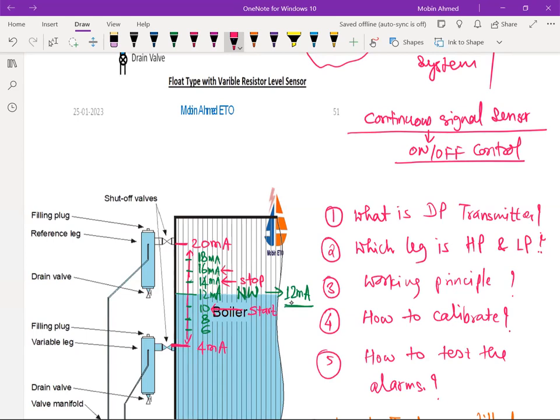Then at 16 milliampere it is going to give the high level alarm, and at 18 milliampere it is going to give the high level trip. In the same way, at 8 milliampere it is going to give a low level alarm, and at 6 it gives the low level trip. So HL or LL: low level trip and low level alarm. Like this it can be used. And if it is a continuous signal, of course the continuous signal will be going, and we can use it for various alarm purposes.